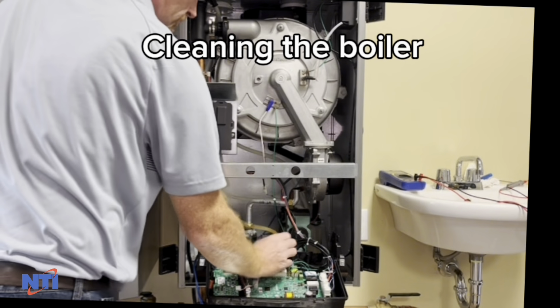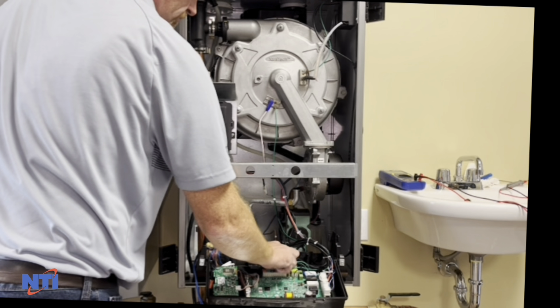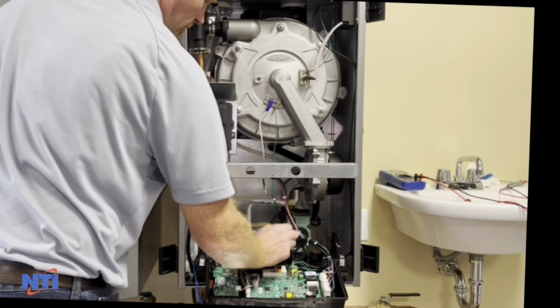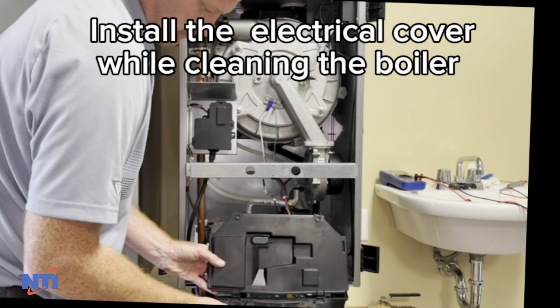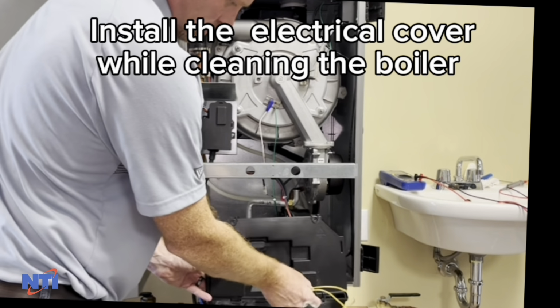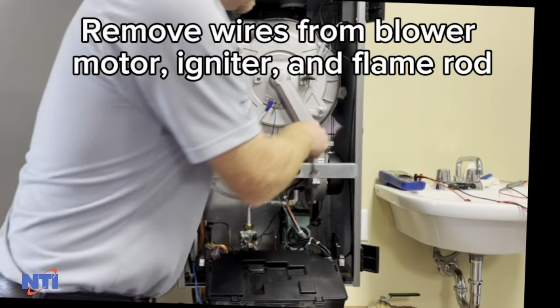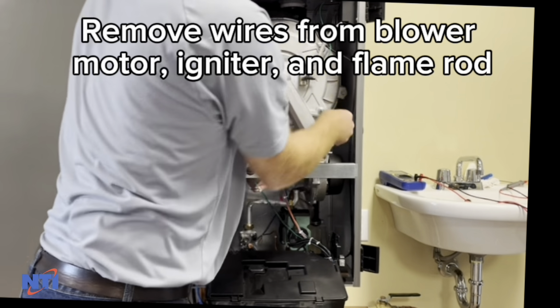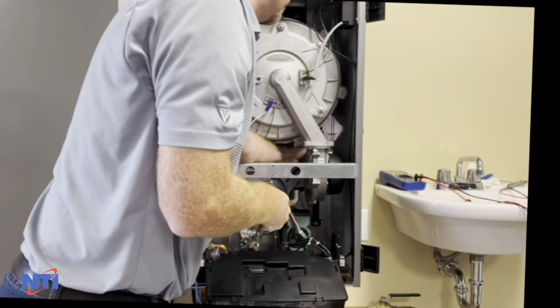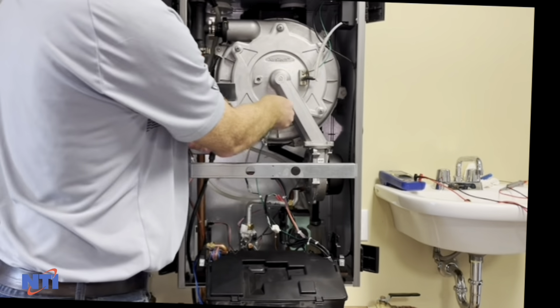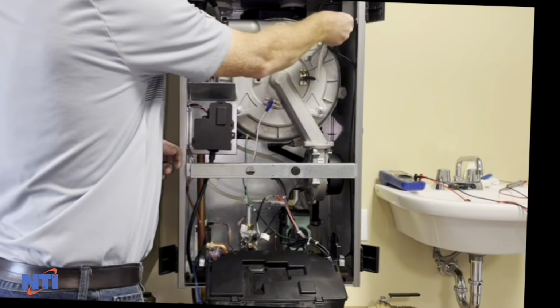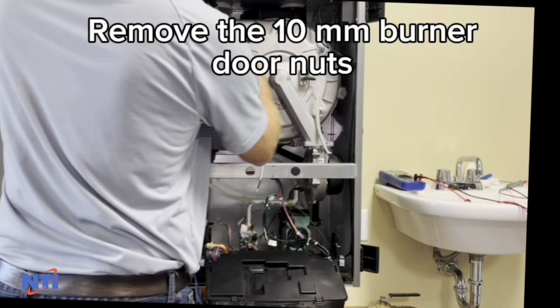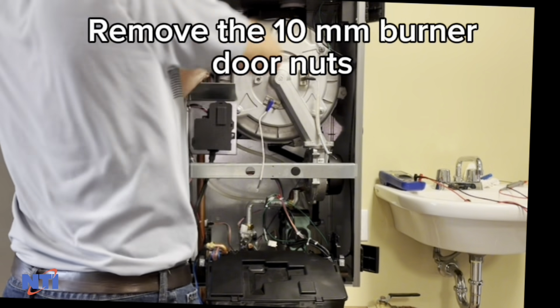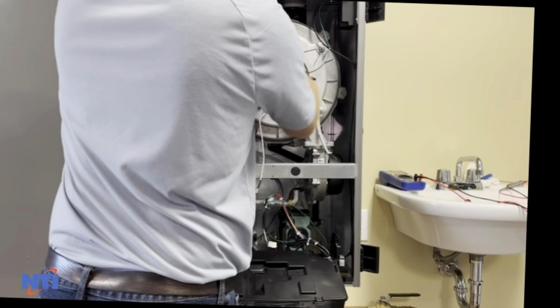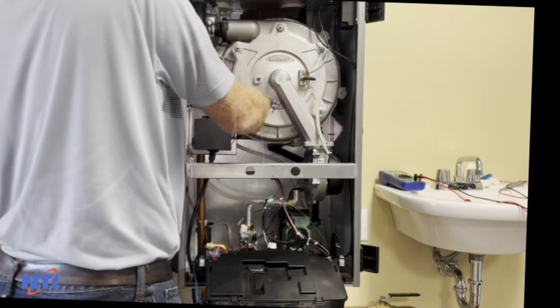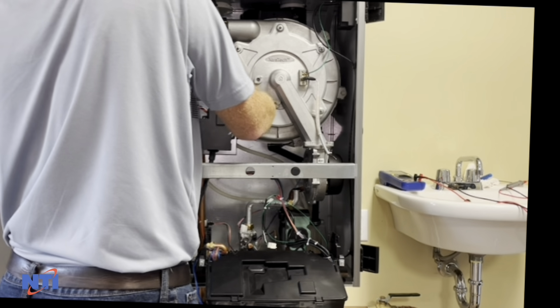A dirty or poorly maintained boiler will cause ignition problems. Before cleaning the boiler, ensure the electrical panel is covered up. Use some rags if needed to prevent water from getting into it. Remove the wires from the flame rod igniter and the blower motor. Then remove the 10mm burner door nuts. Set them to one side. They're required for reassembly. Once the nuts have been removed, remove the burner door and blower assembly as one piece.